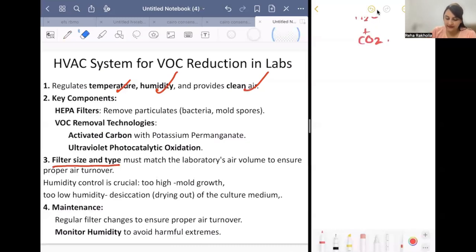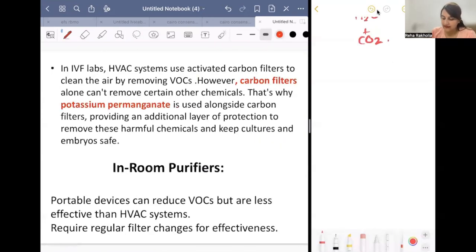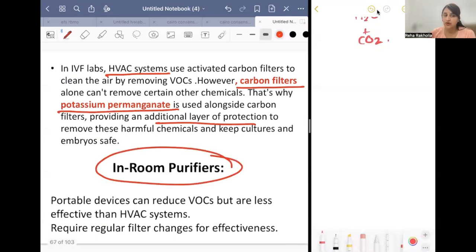For maintenance, we have to maintain the HVAC system with regular filter changes to ensure proper air turnover, and monitor humidity as well. The HVAC system uses both carbon filter and potassium permanganate because together they provide additional protection. In-room purifiers are not as potent as the HVAC system, but can still be used. These are portable devices that reduce VOCs but are less effective than the HVAC system, and they require regular filter changes for effectiveness.